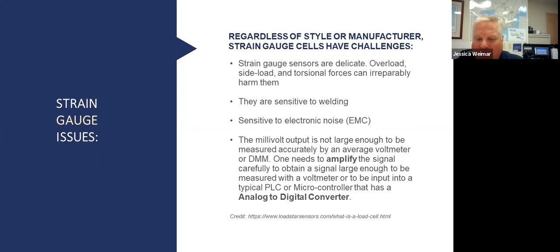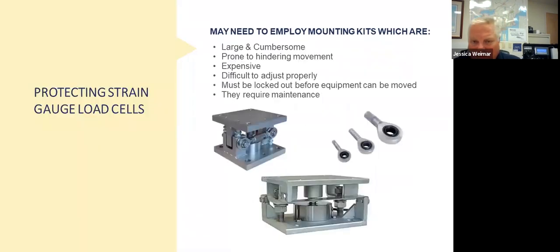And it says that one of the challenges with this is that they've got to amplify the signal, and then they've got to put it through a converter to create a digital signal for the readout or the PLC. And when you do that, converting from analog to digital, you've got the potential to add some error in that conversion. This is also a big issue with strain gauge load cells.